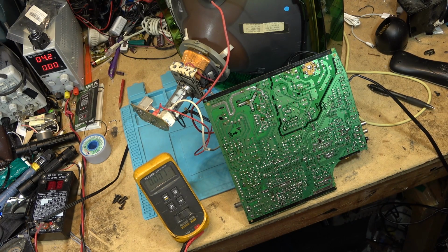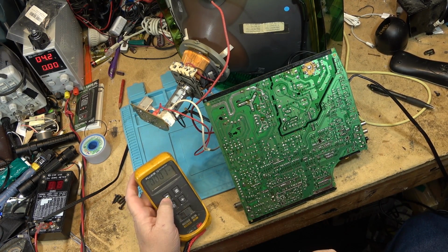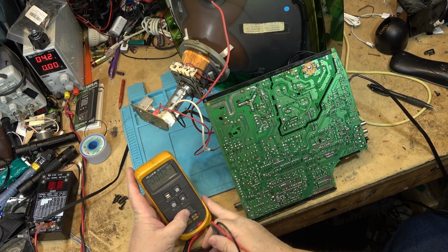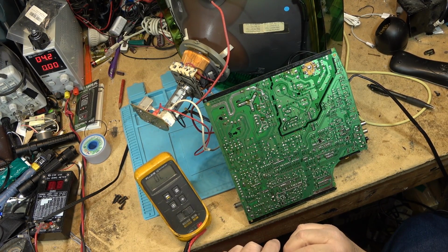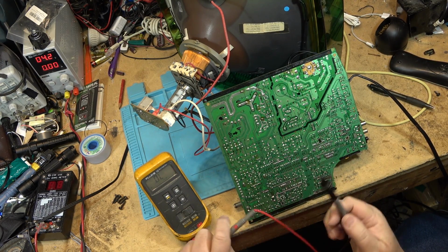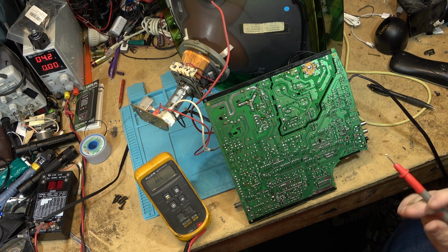But it could be because there's a short and the whole set is everything's being pulled down to nothing here. So let's just take a look and see whether there's any shorts on the DC side, or the transformer, the low voltage side, the isolated side.